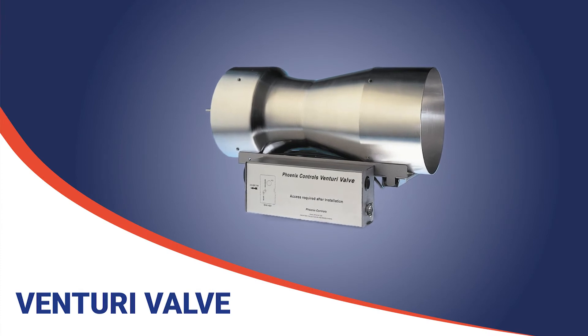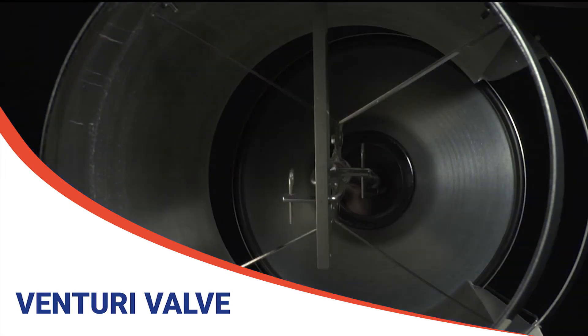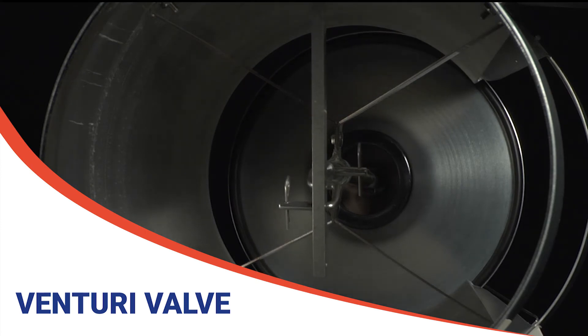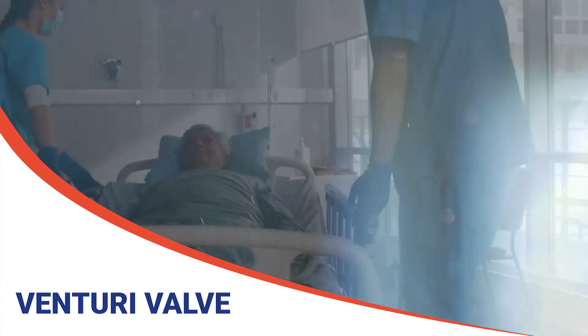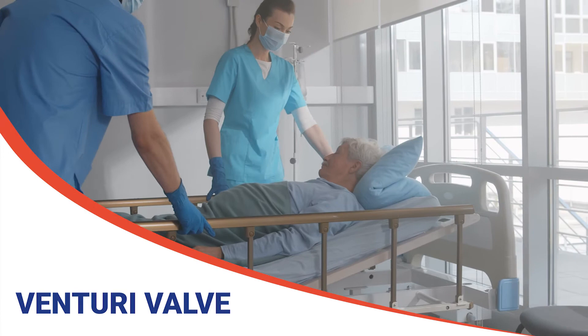The Phoenix Venturi valves are designed to provide an offset airflow between supply and exhaust. The ability to consistently exhaust more room air than airflow being supplied ensures the airborne infectious isolation room will always have a consistent negative room pressurization. With Phoenix Controls, hospitals have less risk in mitigating spread and with the performance and flexibility of the Venturi valve can help maintain safe environments with sustainable practices to reduce HVAC operational and energy costs.